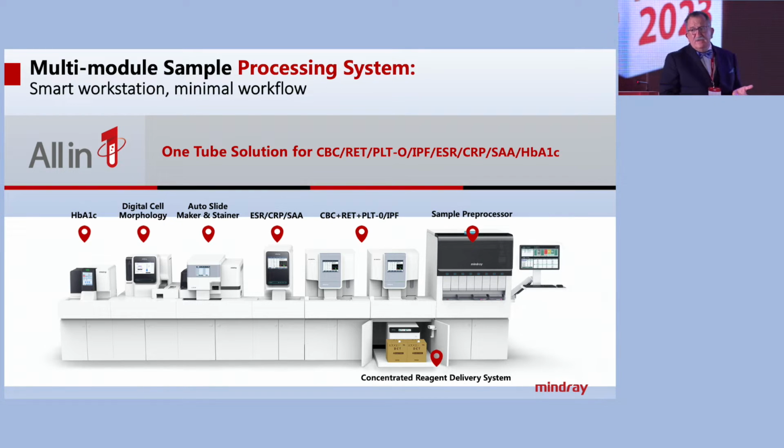That is very important because, as we have seen, many of the parameters are affected by the temperature, and this sample processor keeps the samples at the right temperature to be able to reanalyze with very similar results after several hours.